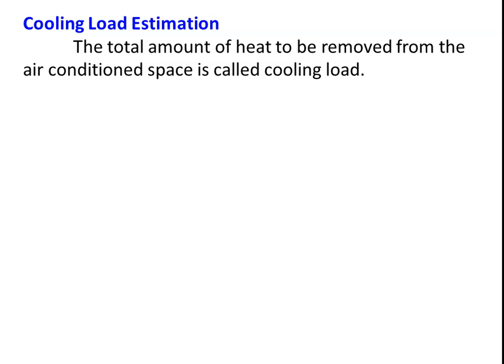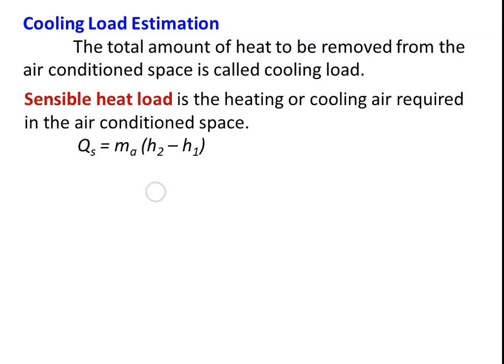Initially we discuss certain parameters, certain definitions on the cooling load calculation. Then we will see what the different types of cooling load are. The first type is sensible heat load. Sensible heat load is the heating or the cooling of air required in the air conditioned space. The sensible heat load is due to the heating or cooling of air. We already discussed the process called sensible heating or sensible cooling. So the amount of heat removed and the amount of heat added is the sensible heat load. This is calculated as QS equal to MA into H2 minus H1. MA is the mass of the air, H2 is the enthalpy at the outlet, and H1 is the enthalpy at the inlet.